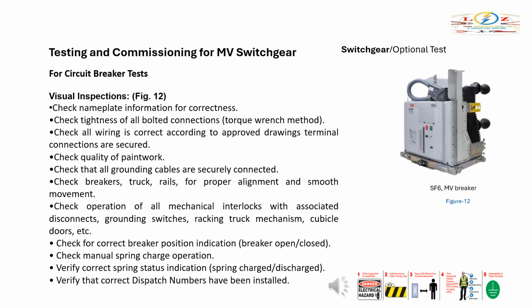For circuit breaker tests, visual inspection. Check nameplate information for correctness. Check tightness of all bolted connections, torque wrench method. Check all wiring is correct according to approved drawings. Terminal connections are secured. Check quality of paintwork. Check that all grounding cables are securely connected. Check breakers, truck, rails for proper alignment and smooth movement.